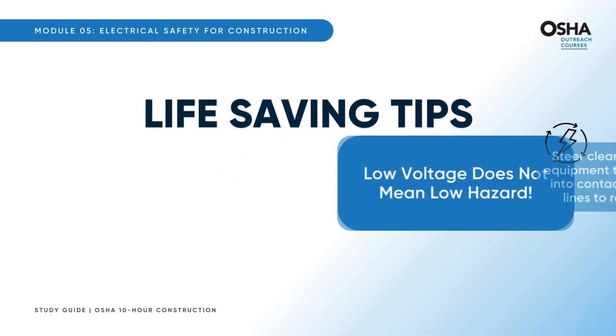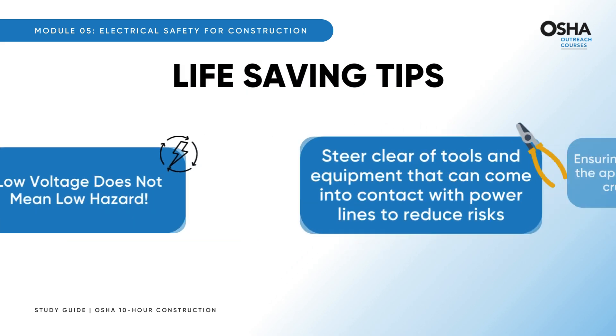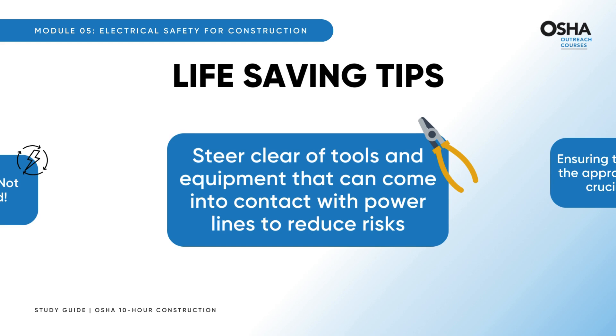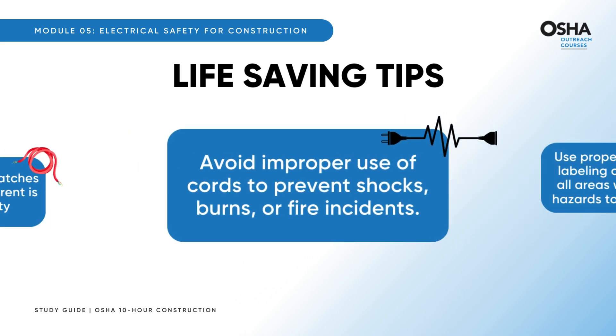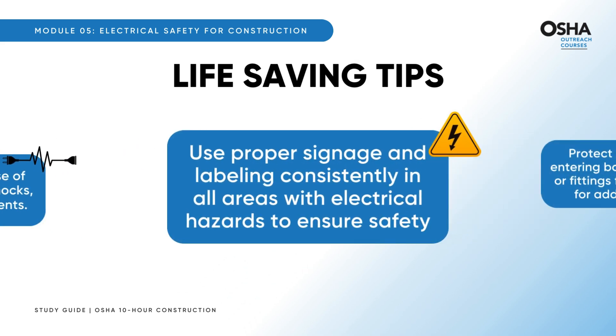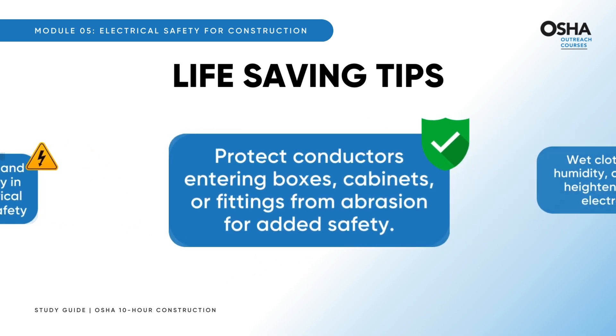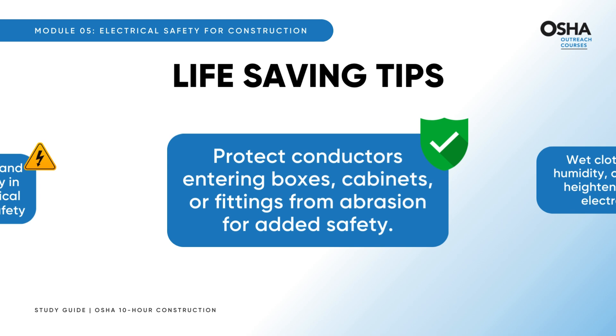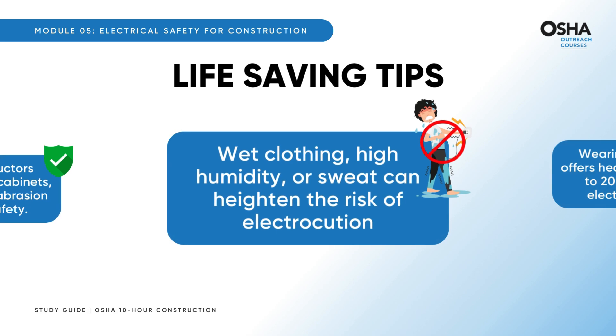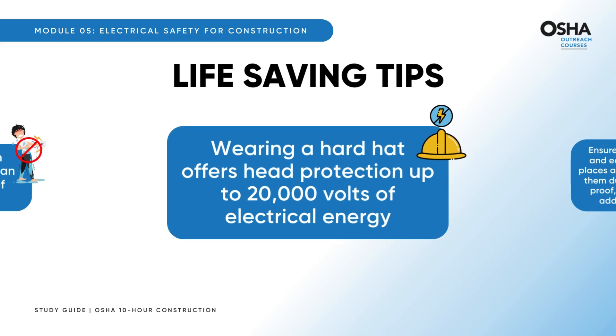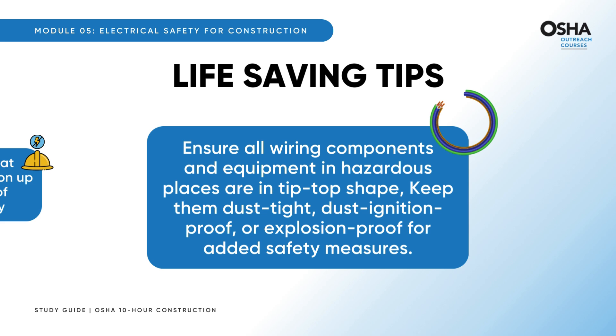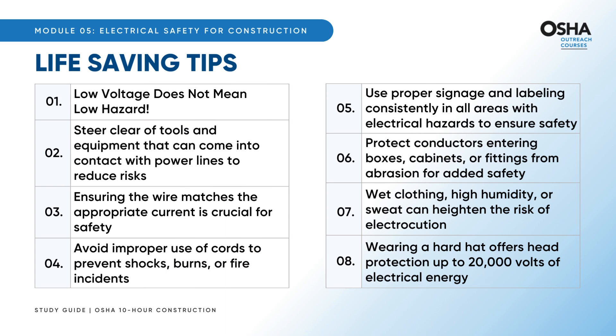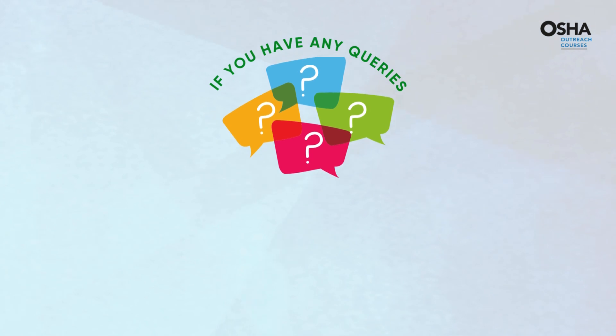Essential life-saving tips: always remember, low voltage does not mean low hazard. Steer clear of tools and equipment that can come into contact with power lines. Ensure the wire matches the appropriate current. Avoid improper use of cords to prevent shocks, burns, or fires. Use proper signage and labeling in all areas with electrical hazards. Protect conductors entering boxes, cabinets, or fittings from abrasion. Note that wet clothing, high humidity, or sweat can heighten the risk of electrocution. Wearing a hard hat offers head protection up to 20,000 volts. Ensure all wiring components and equipment in hazardous locations are dust-tight, dust-ignition-proof, or explosion-proof.